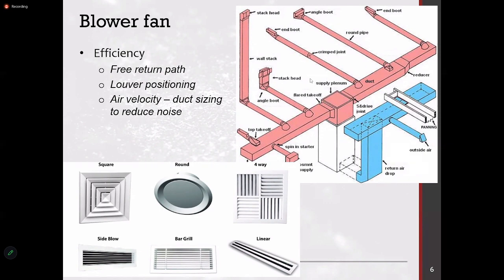So duct sizing is critical because most of the time the designers or the investors or the contractors tend to reduce the duct sizes to ensure their investment or their contract value is reduced, but the problem you will come across is you will have a lot of whistling. And they will even look like jets when they come out of the diffusers. So if a person is directly seated there, then he will get a direct blow. So that is also not recommended. You have to ensure that the distribution is equally distributed.